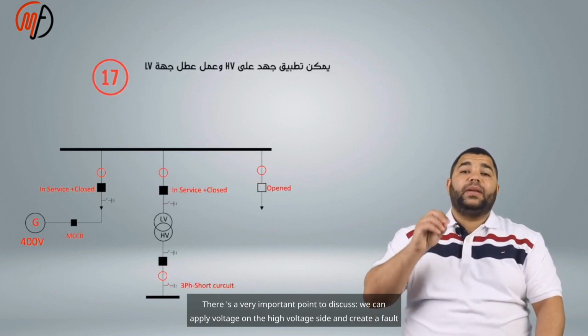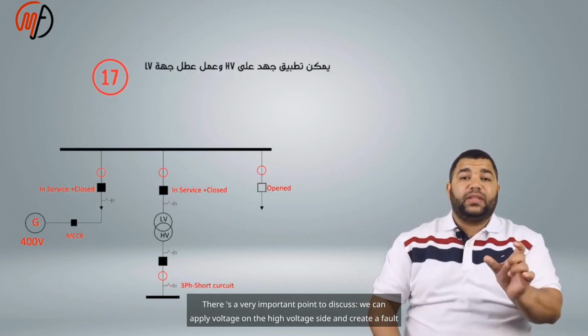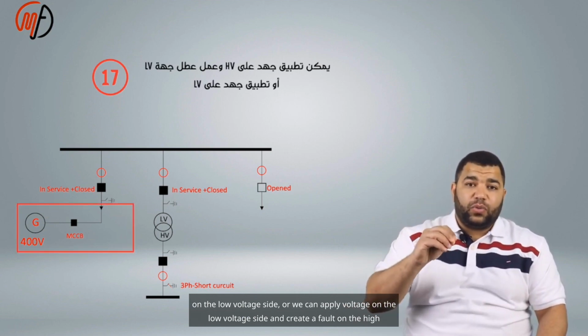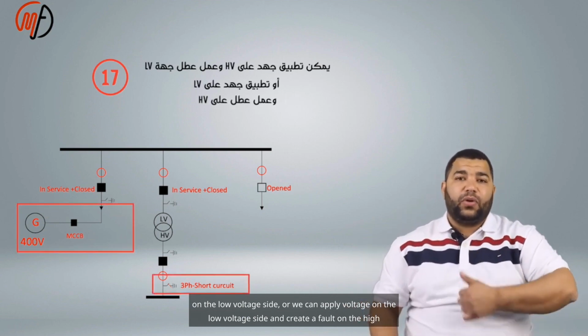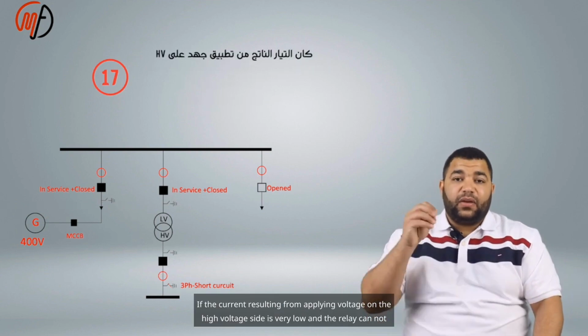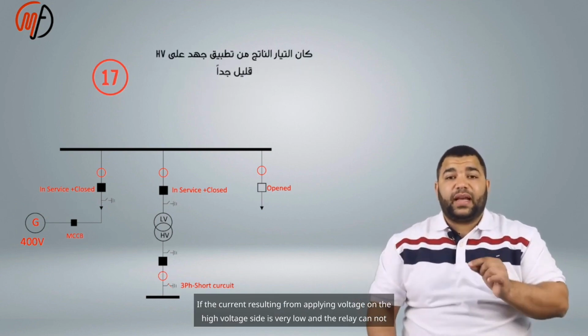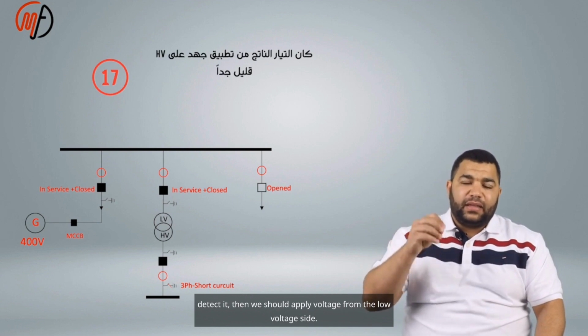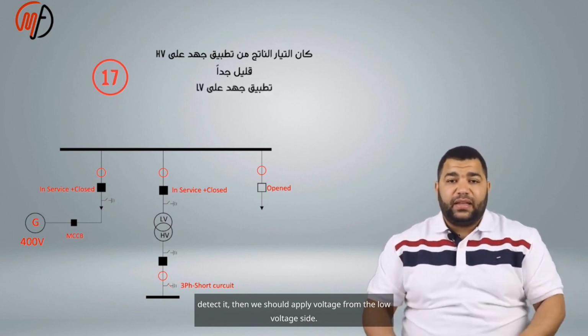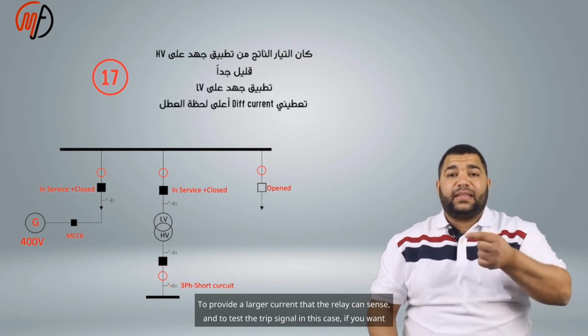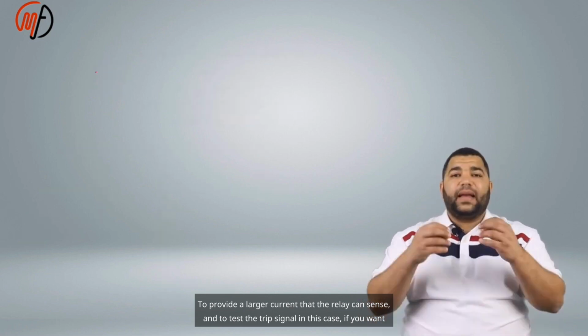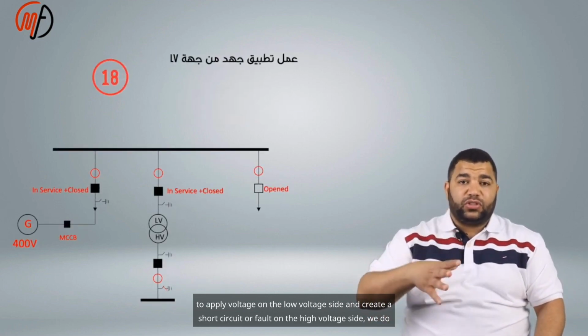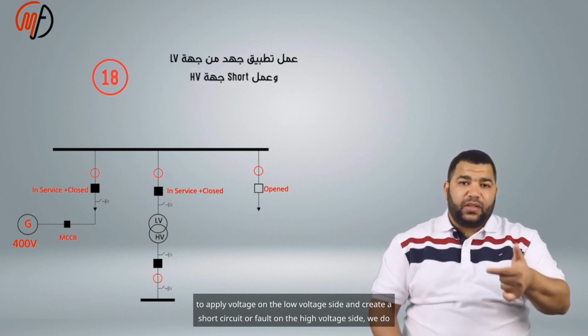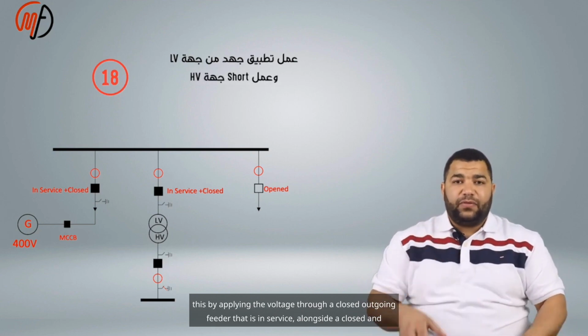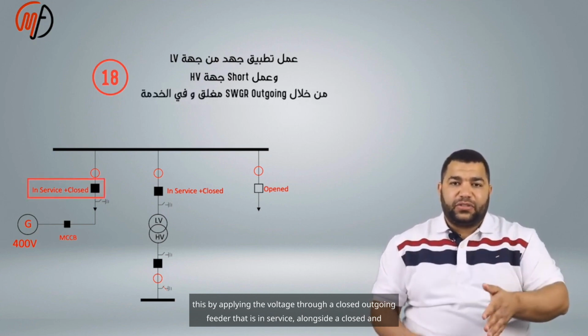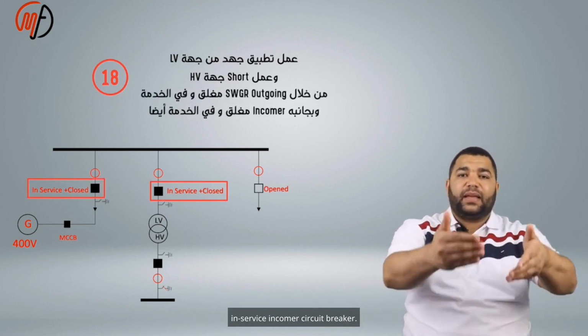There's a very important point to discuss. We can apply voltage on the high voltage side and create a fault on the low voltage side, or we can apply voltage on the low voltage side and create a fault on the high voltage side. If the current resulting from applying voltage on the high voltage side is very low and the relay cannot detect it, then we should apply voltage from the low voltage side to provide a larger current that the relay can sense, and to test the trip signal in this case. If you want to apply voltage on the low voltage side and create a short circuit or fault on the high voltage side, we do this by applying the voltage through a closed outgoing feeder that is in service, alongside a closed and in-service incomer circuit breaker.